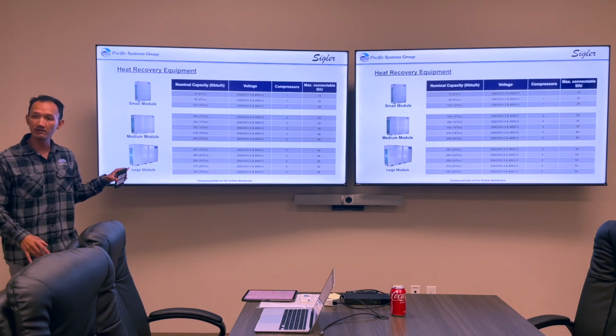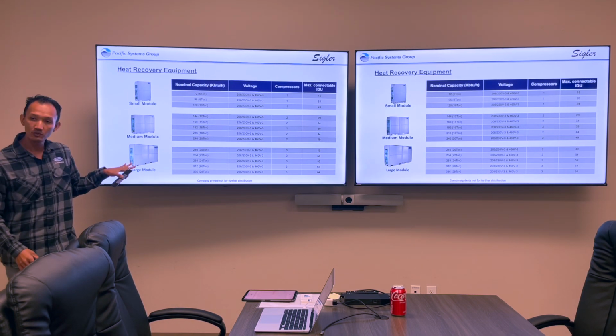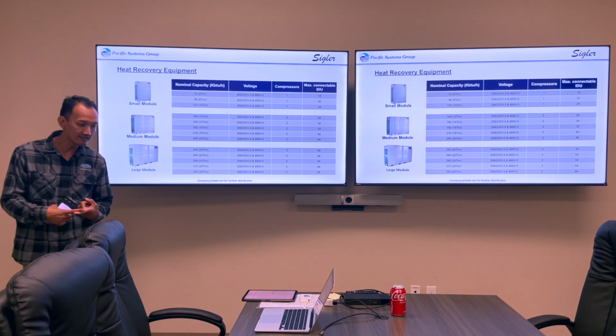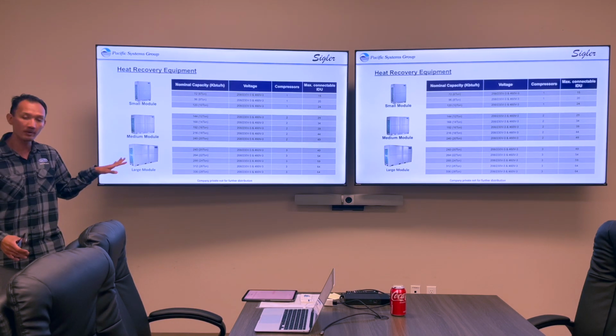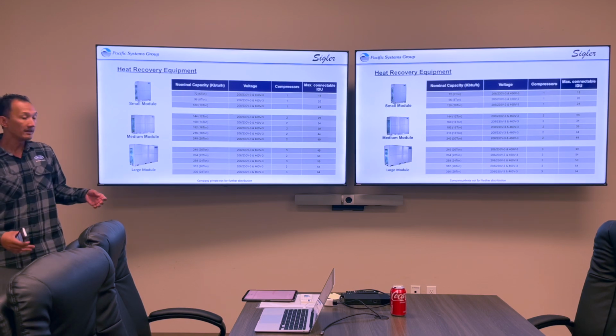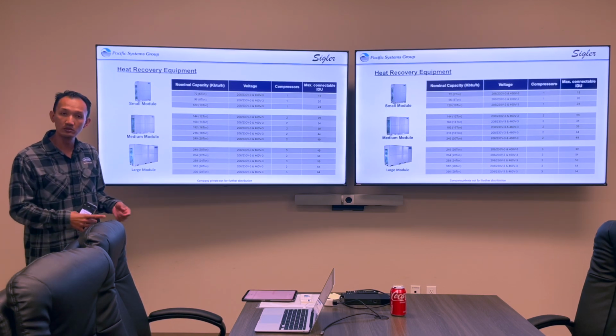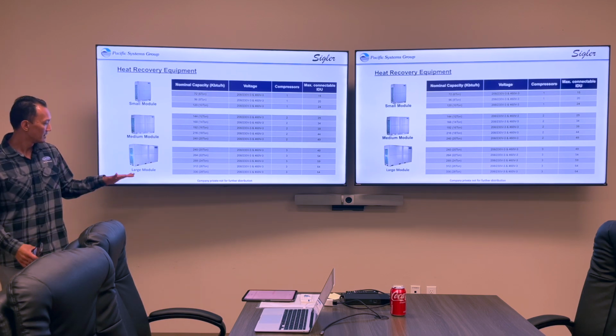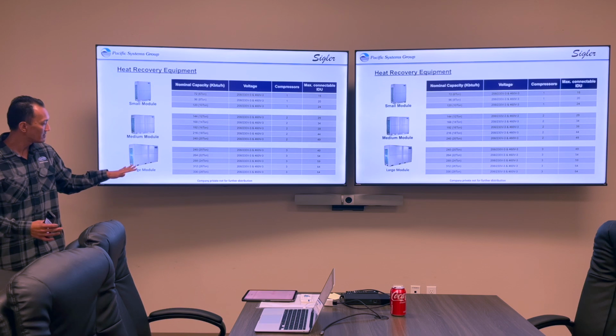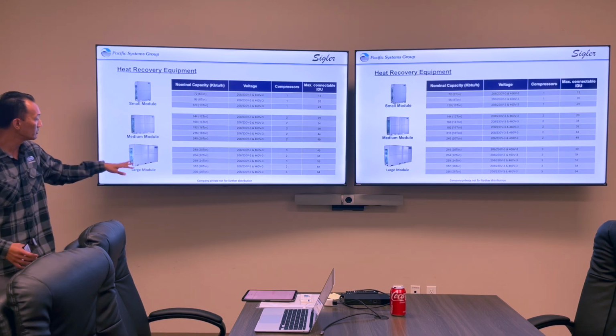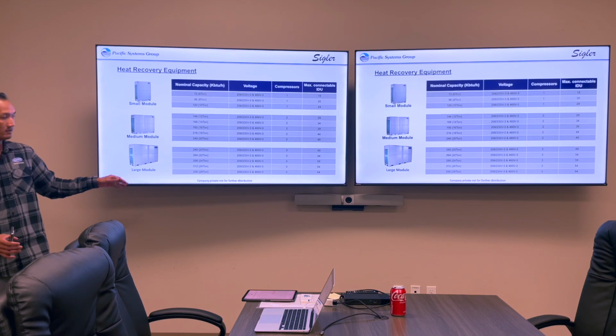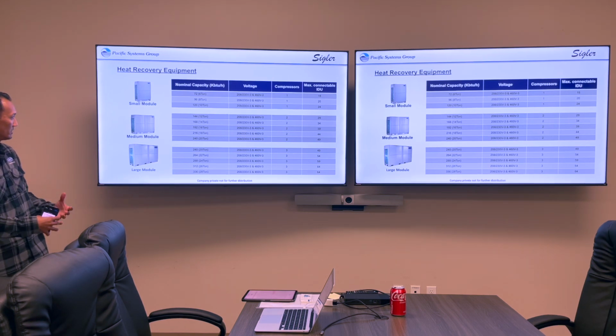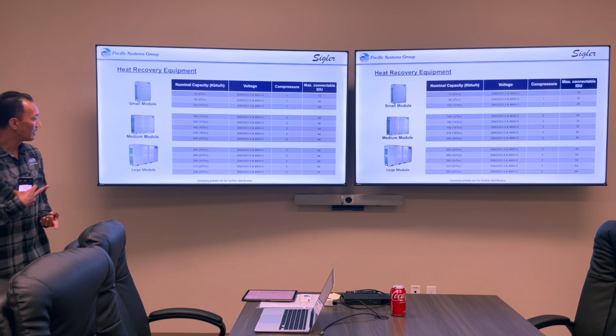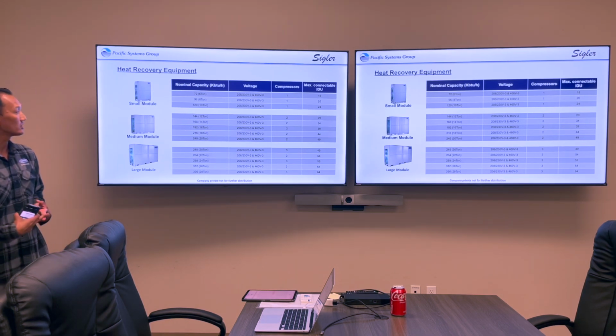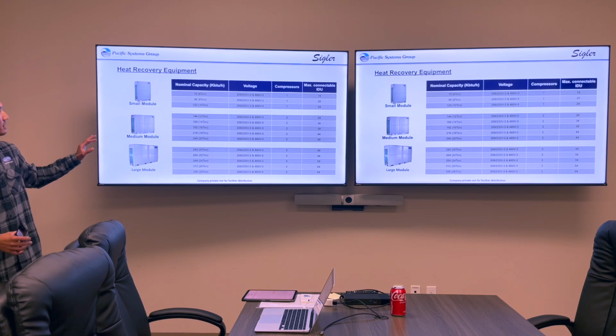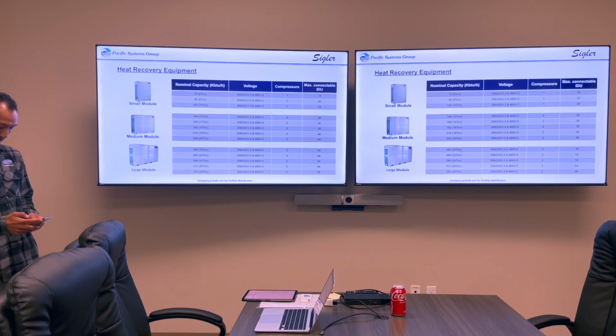So these come like this from the factory. The advantage of doing it this way is that the contractor or the installer has less work to do out in the field. They don't have to pipe 2 or 3 modules together. They don't have to run electrical to 3 individual modules or condensers. The advantage here is that there's time saved. You don't need to pipe them out in the field, and they only require 1 electrical connection because they come like that from the factory as 1 module. So less time for the contractor, for the installer, to install these, and that's unique on our Carrier 2-pipe heat recovery line.